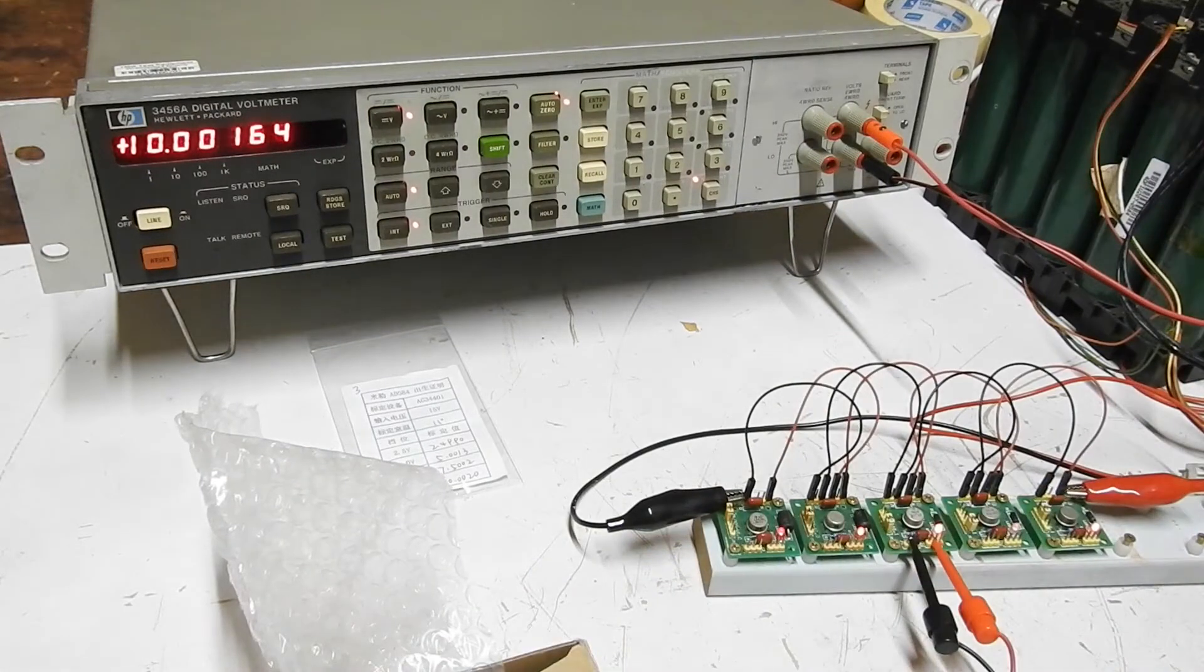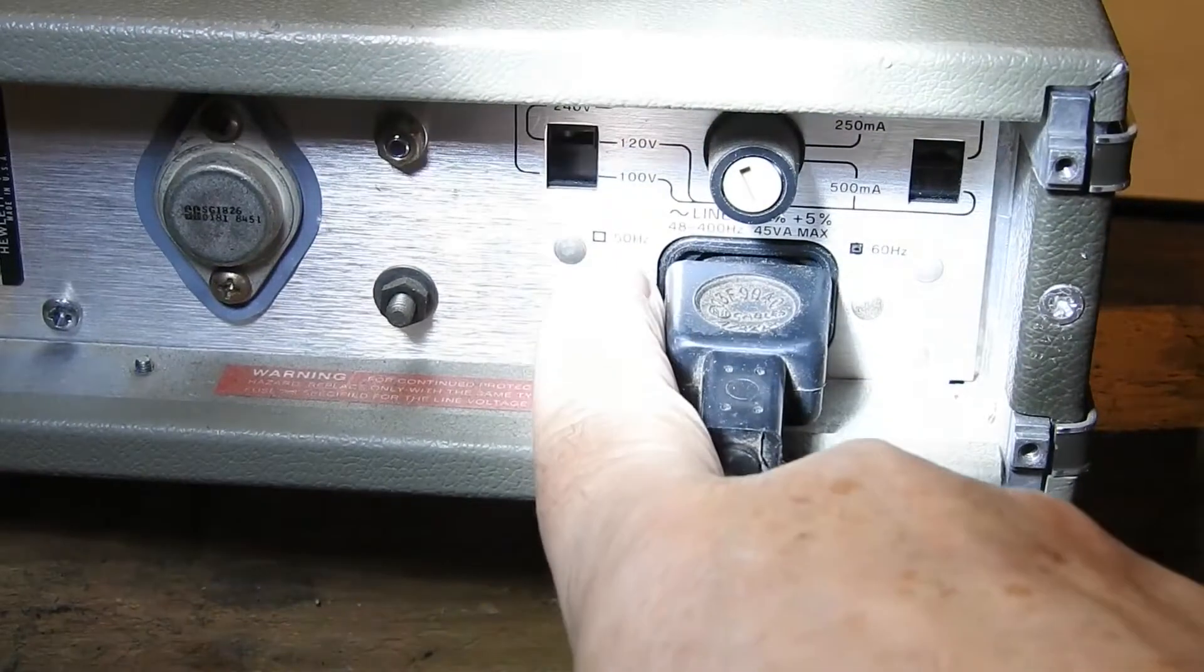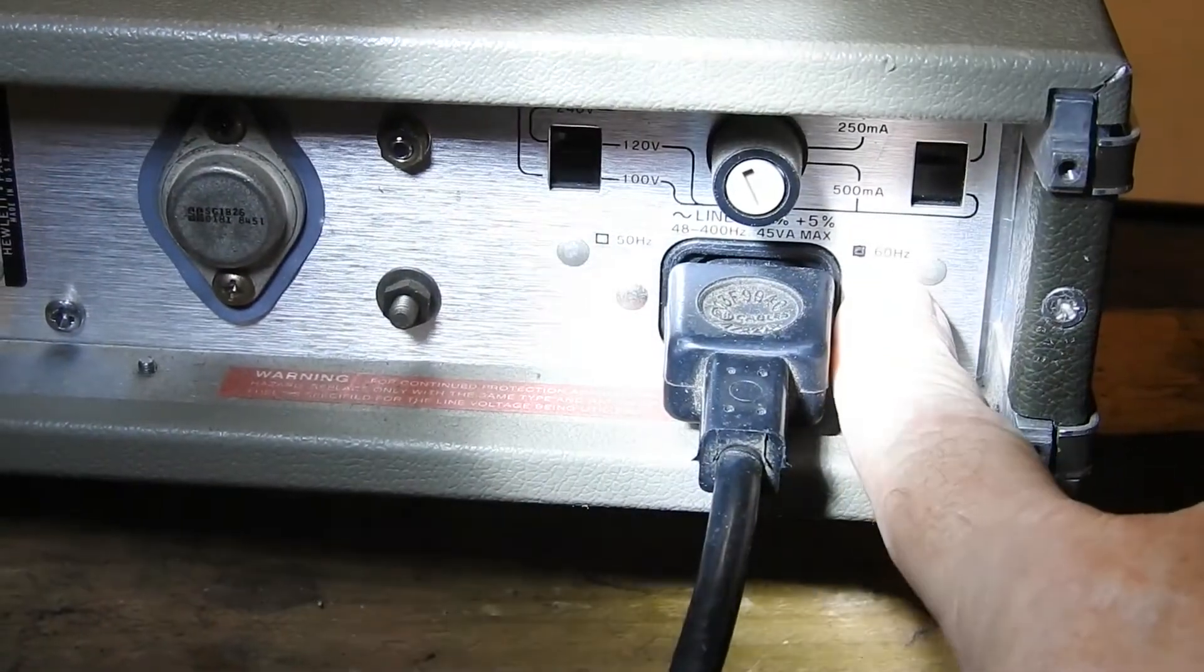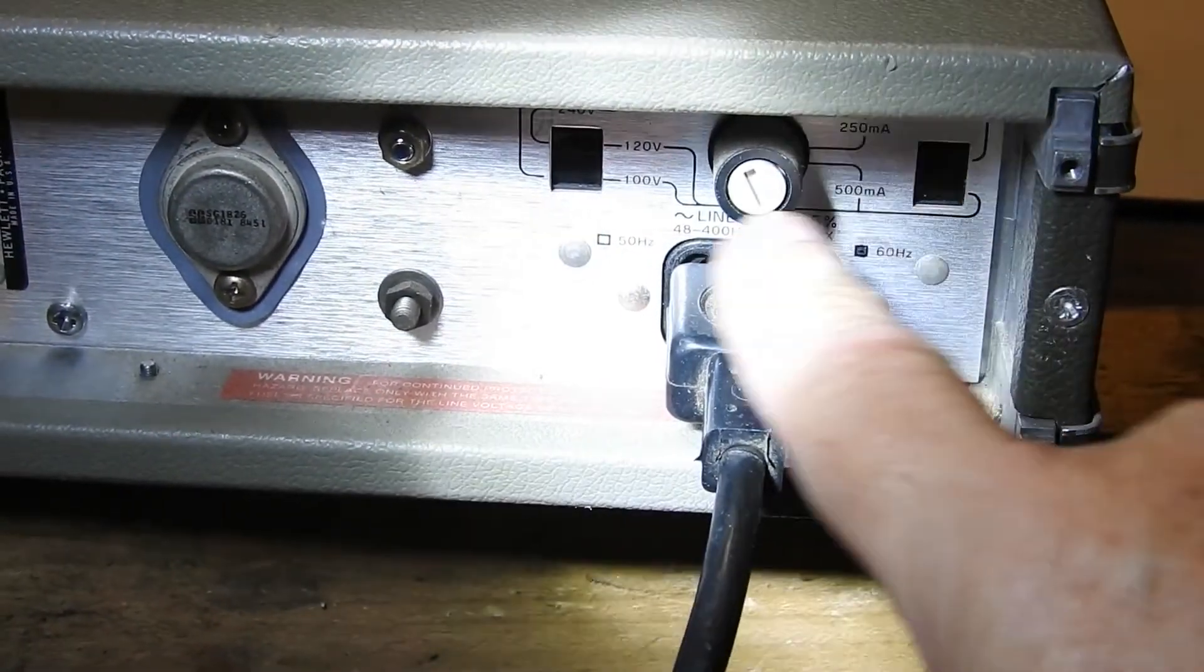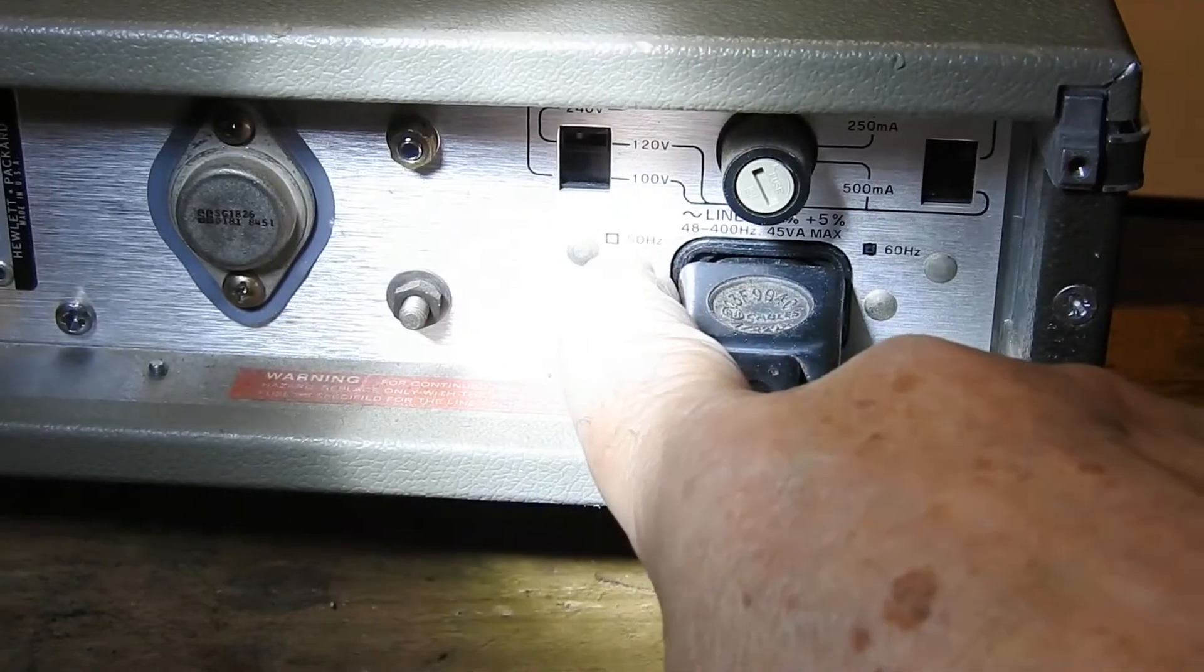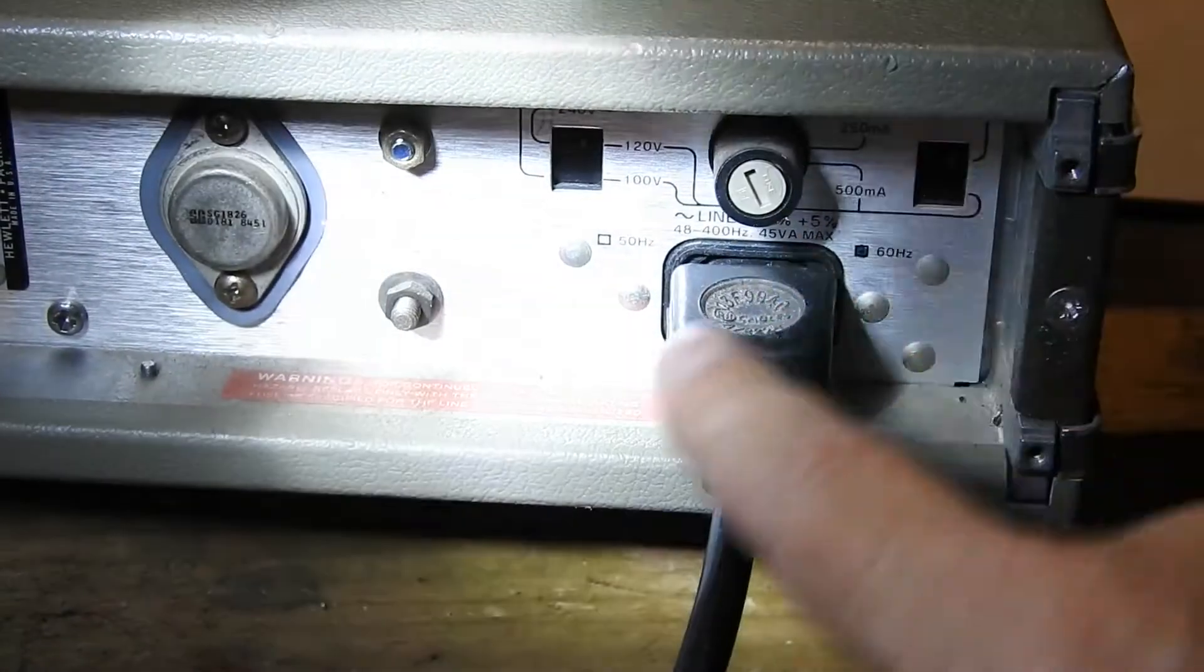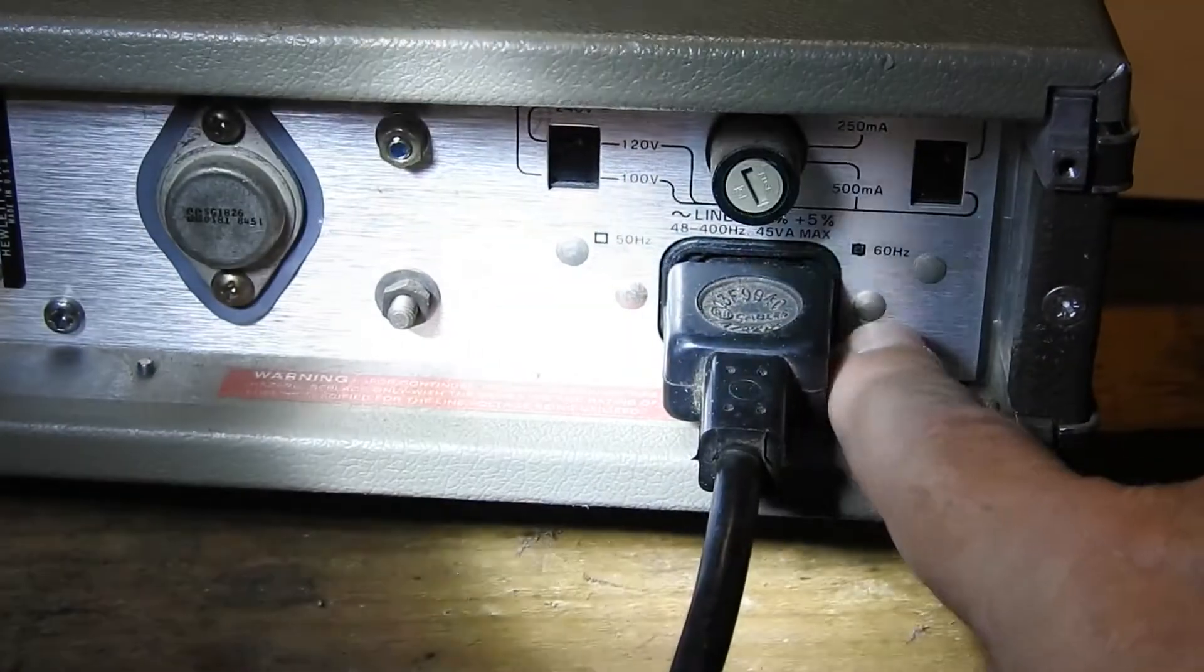I'm going to change the crystal for one that matches the 50Hz line frequency that we have here in Australia. If we look at the back of the unit, you can see there it's got 50Hz and 60Hz, and the 60Hz is marked, and not the 50Hz. That means that it's got the 60Hz crystal in there.